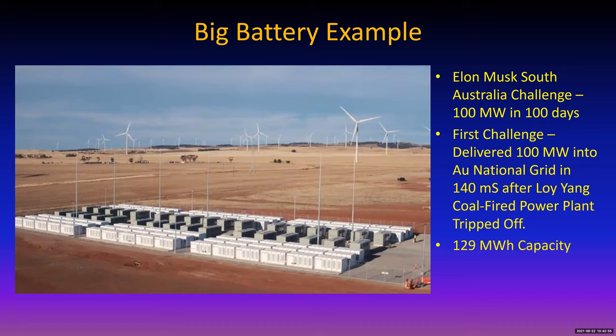This has a 129 megawatt hour capacity. In other words, it will deliver 100 megawatts for 1.29 hours, or 10 megawatts for 12.9 hours, and actually a little more than that if you want to use the energy that way. So there are some big batteries out there, and they've been proven to work just fine.